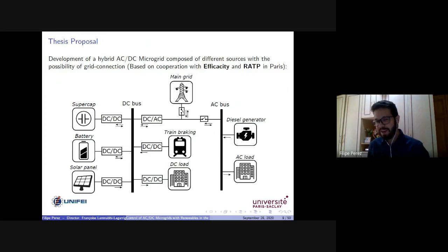Yes. So if we think about the train system as a whole, as a lot of operating train systems nowadays, they already have a strategy to reduce the impacts of the train braking, like when a train is accelerating, the other is decelerating, such that the power injected by one train goes to the other train. But that is not enough to provide the regulation of the voltage, because the trains are supplied by DC voltage. So they need the power converters. And in the system, we can see that the power converters are suffering from oscillations in voltage.